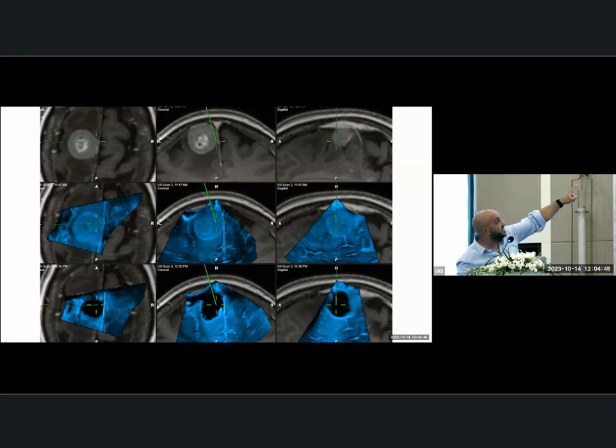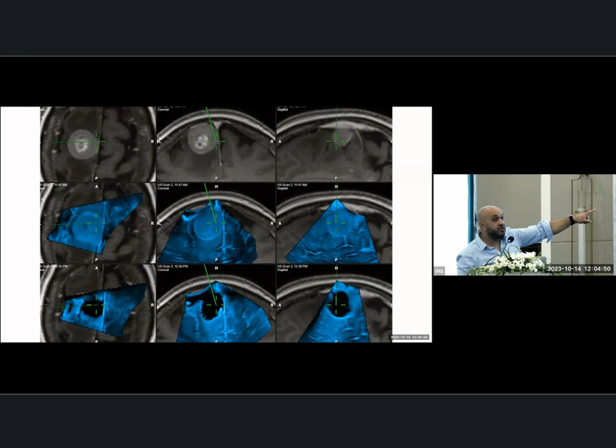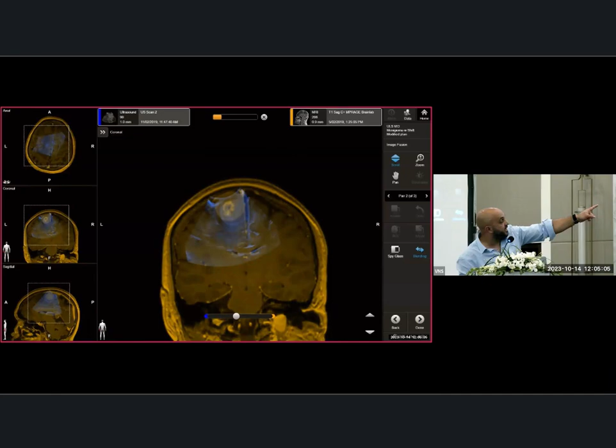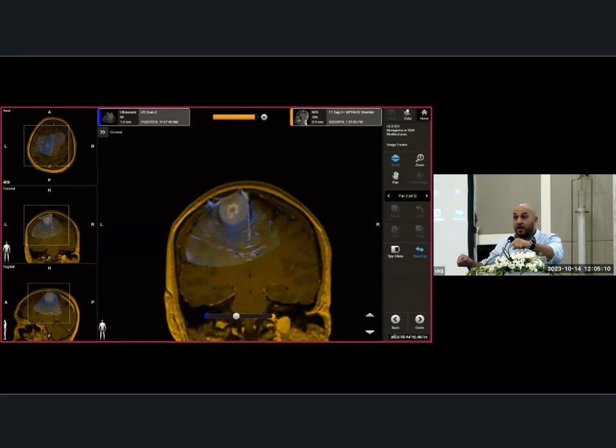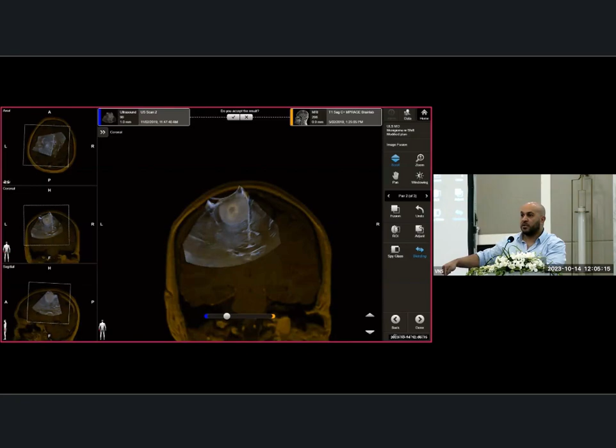Now, as I showed you before, you can see the top image. The marker I have is not in the same place in real time. Now, the Brainlab machine can correct for that. And I'll just show you this very quickly. You can see here, this is the MRI, this is the ultrasound and MRI scan, and you can see the falx is separated by almost 1 centimeter there. And now what the computer will do is it will correct it. It will bring the MRI scan to match the ultrasound, because the ultrasound is the correct one. It's a live image. It has to be correct. The MRI is off. So the computer has now corrected and so it's allowed for the shift and the registration area, and it's brought the MRI scanner back into where it should be.